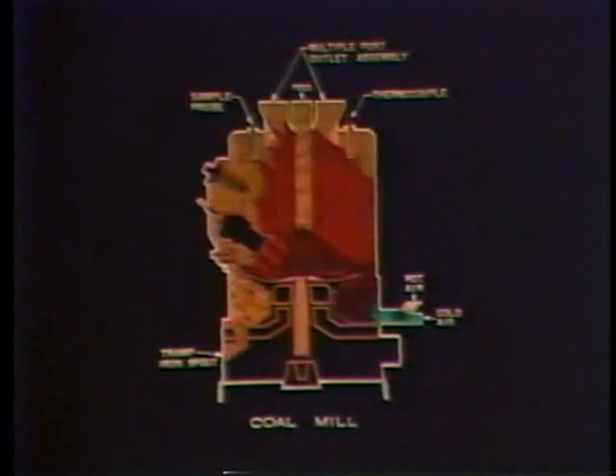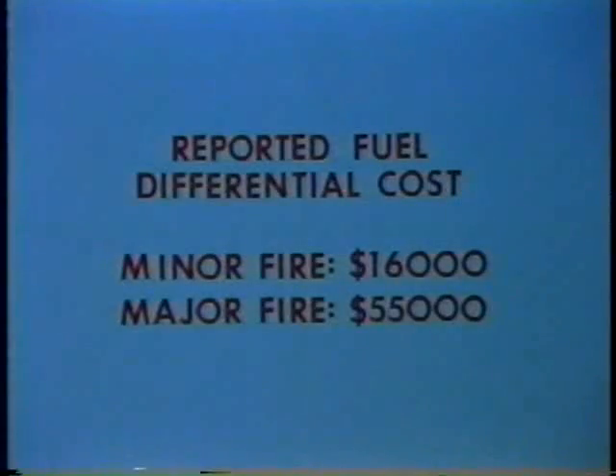Coal fires can be extremely detrimental to safety and operational stability, and they're often quite costly. One southwestern utility company has estimated losses of $4,000 per hour of time that one of their pulverizers is out of service. Minor fires cost about $16,000 for 4 hours of downtime, and major fires can exceed $50,000. These figures are based upon fuel differential cost and do not include the cost of cleanup and repair.